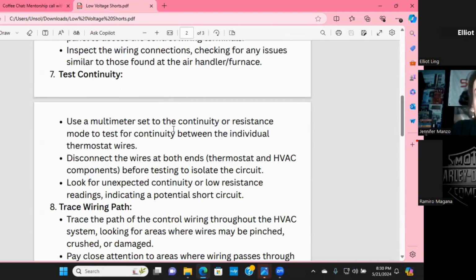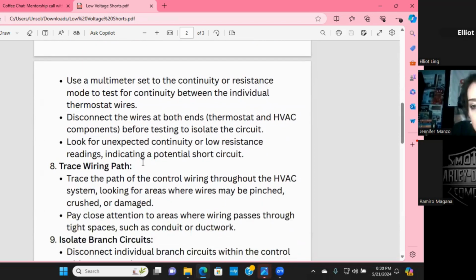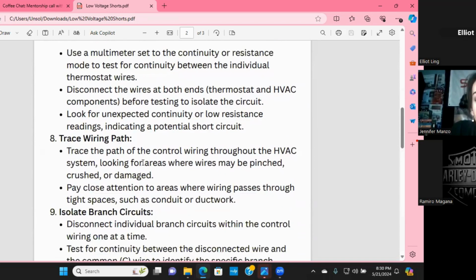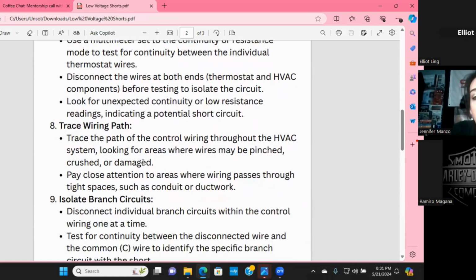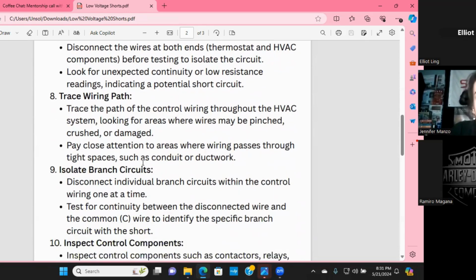And then test continuity. Use a multimeter set to continuity or resistance mode to test for continuity between the individual thermostat wires. So you want to test for continuity here. You're going to disconnect the wires at both ends, the thermostat and the component, and then you're going to isolate the circuit. You're going to look for any unexpected continuity or low resistance readings. So if you don't have your resistance, or you have a weird number for your continuity, you have a bad circuit. Somewhere in that circuit, something's wrong. Usually it's the wire if you're testing for continuity and do not have it.